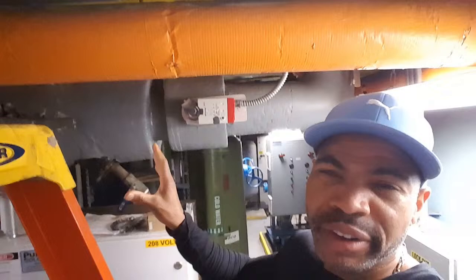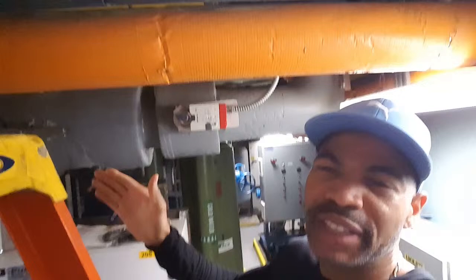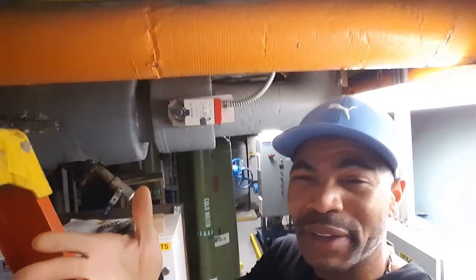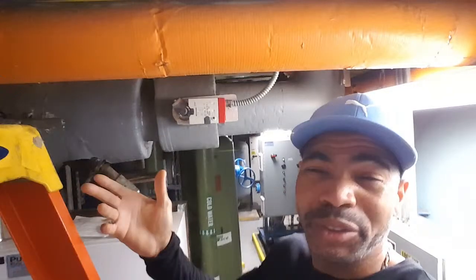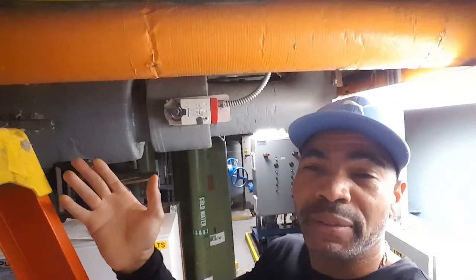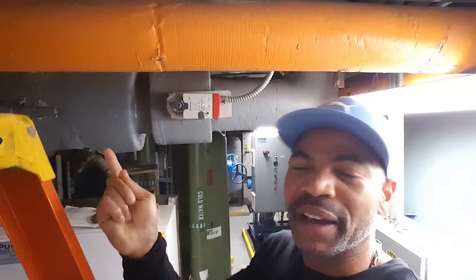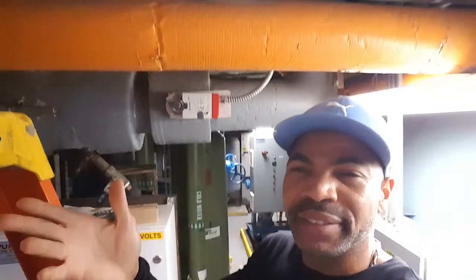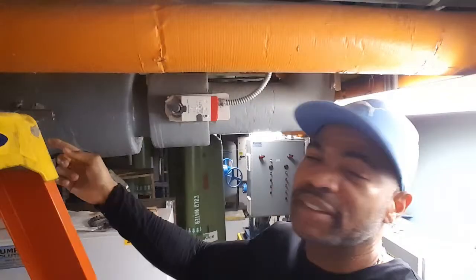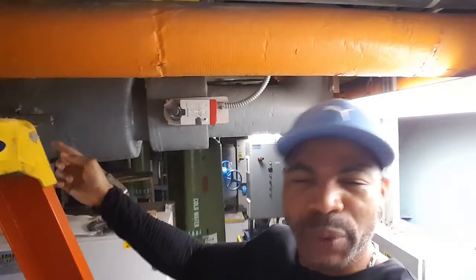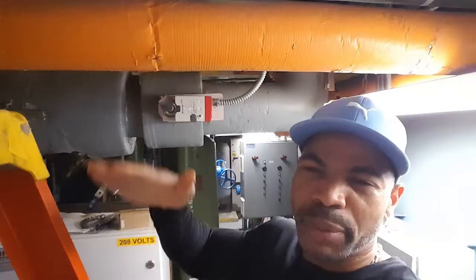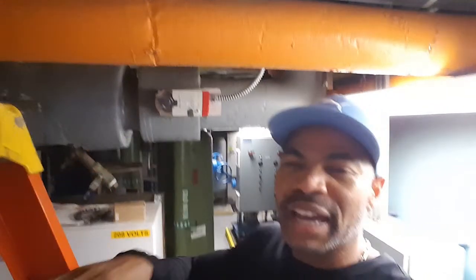We have it on water and even sometimes on steam. On steam, it's to bypass a valve. Say for example your valve is defective and you need to bypass the steam around that valve, or you lose control of the valve. You have no control going to it, you can't open it. The guy may have a bypass to send the steam around the valve. So it's as it says, bypass. In this case, rather than going straight up, it goes right into the return, and thus you'll see the pressure balances out.